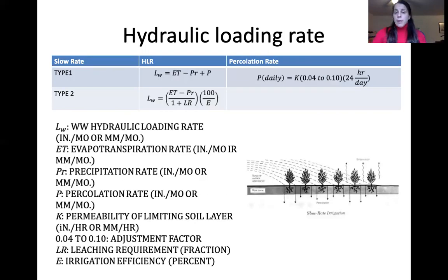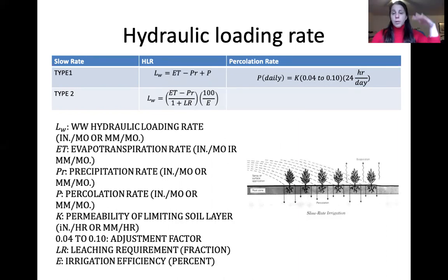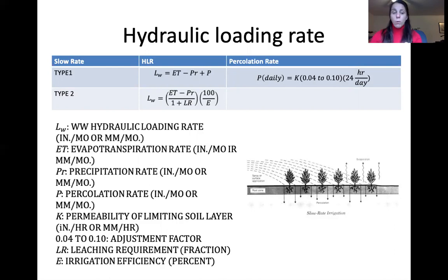For hydraulic loading rate calculations: type one considers evapotranspiration minus precipitation plus percolation rate through the soil. The daily percolation rate equals the K value (permeability of the limiting soil layer in inches per hour) times an adjustment factor of 0.04 to 0.1, times 24 hours per day. This gives a daily rate convertible to yearly or monthly. The hydraulic loading rate is based on a monthly water balance using the wettest year in the past 10 years.